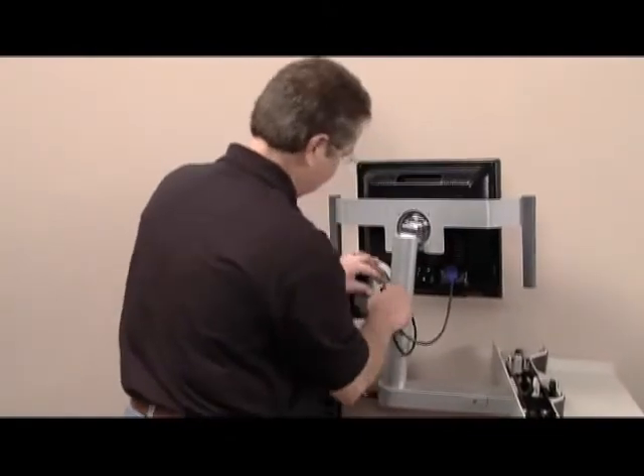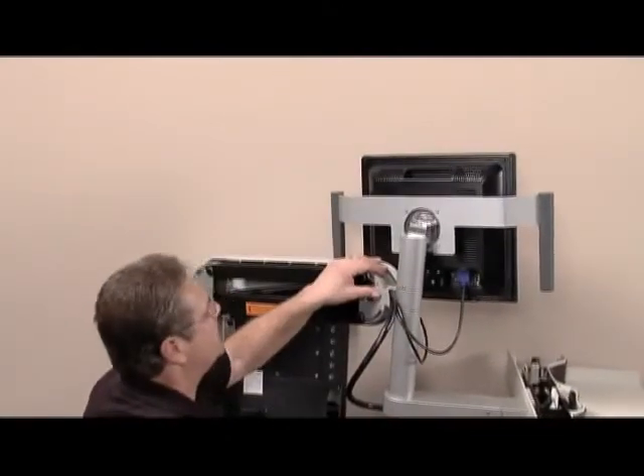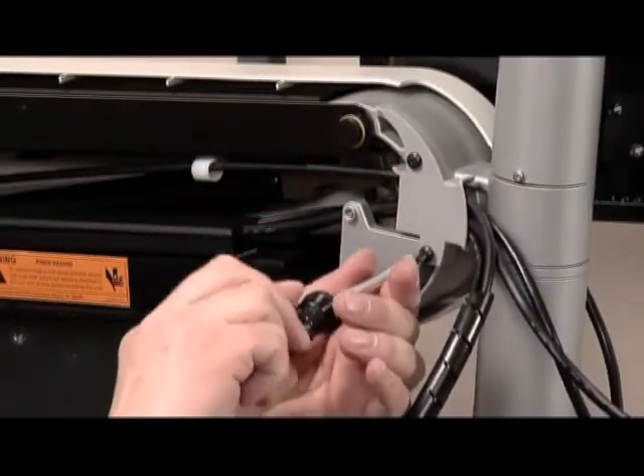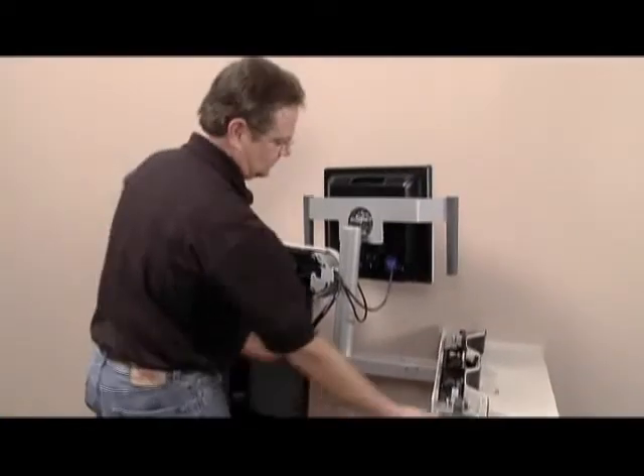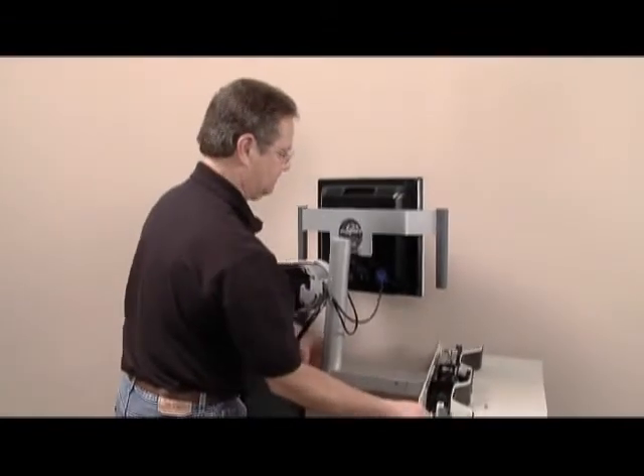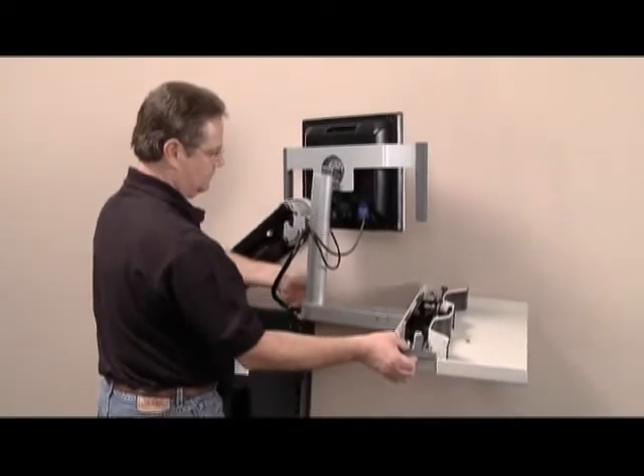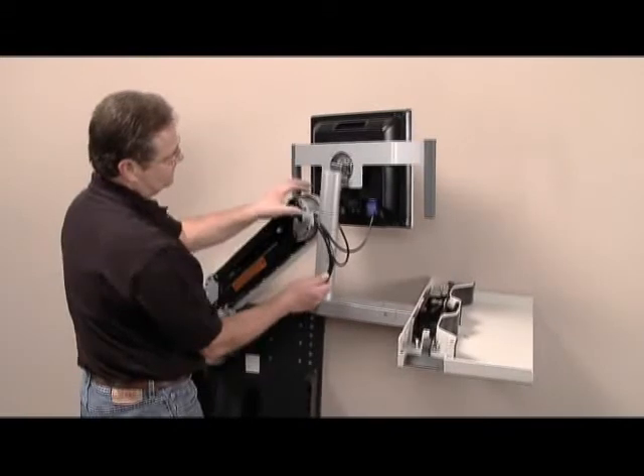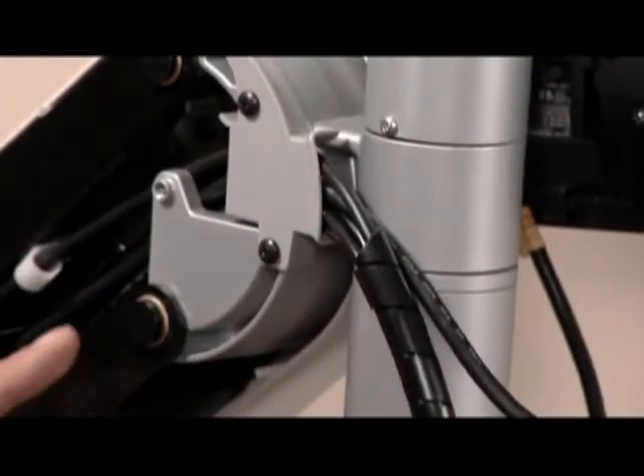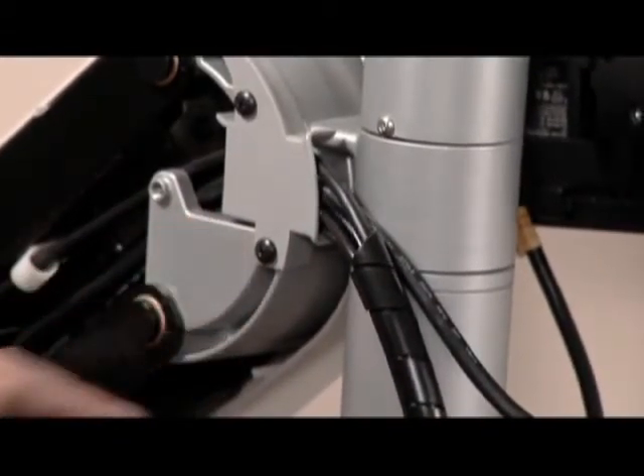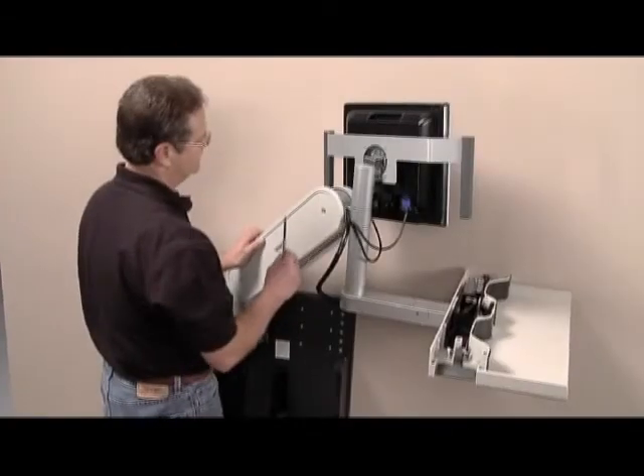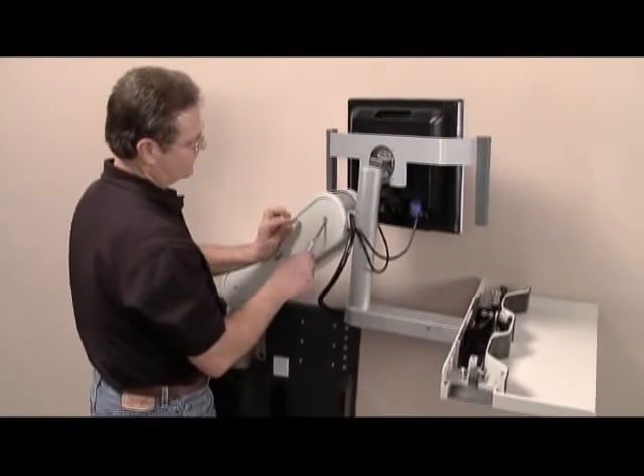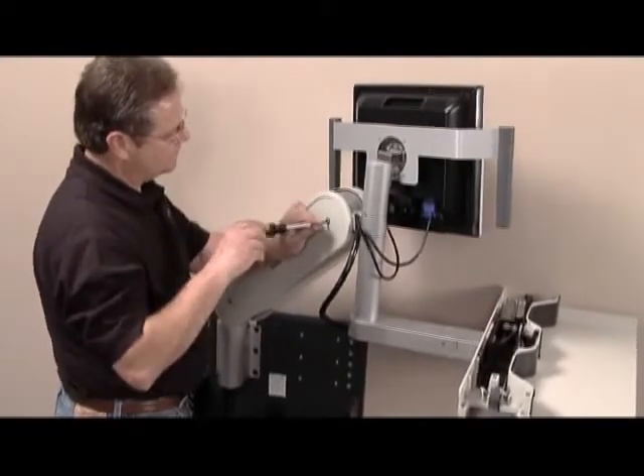Make sure the cables lay flat inside the arm, free of twists or binds. Check to see that there's enough cable slack by moving the ShareLink up and down. Down low, there's a lot of slack, but it's needed because, when ShareLink moves up, the cable wrap must stop short of the grommet so the unit won't bind. Now that you know the cables have the right amount of slack, reinstall the arm cover.